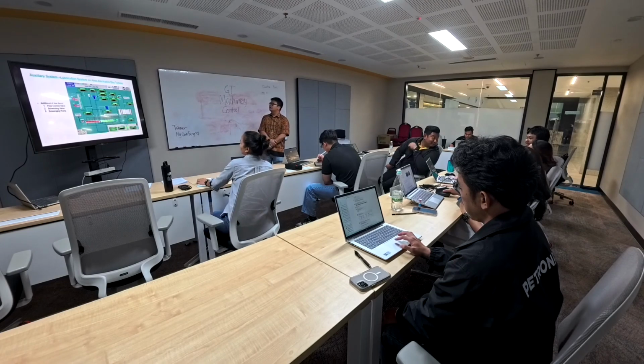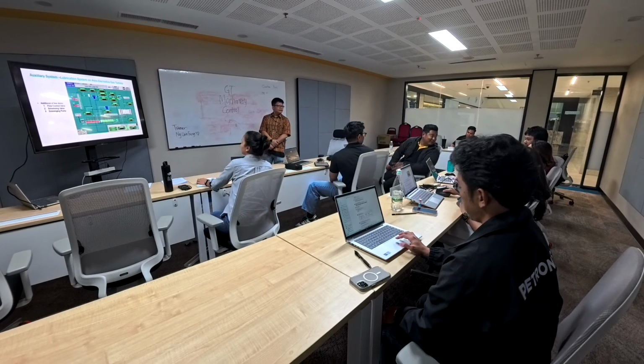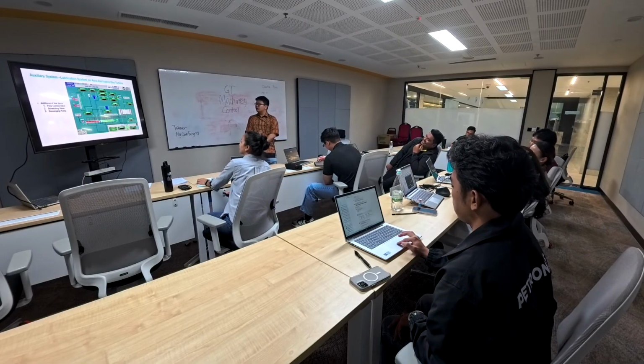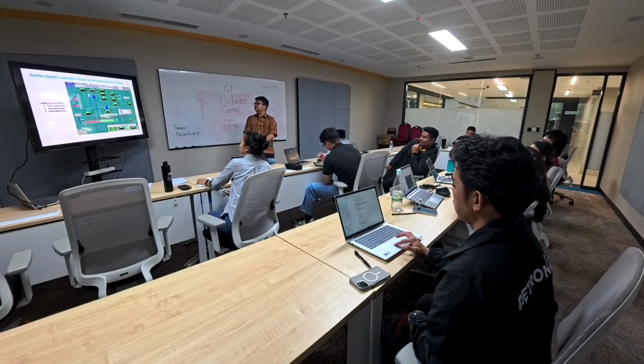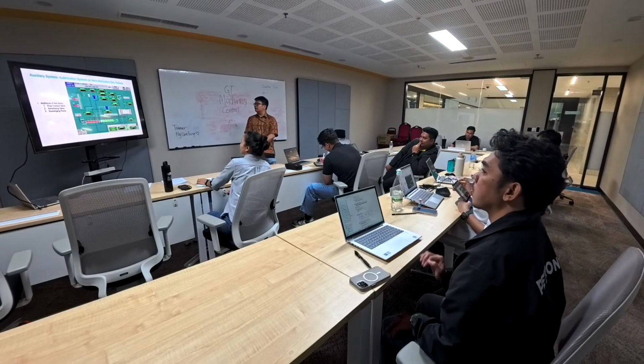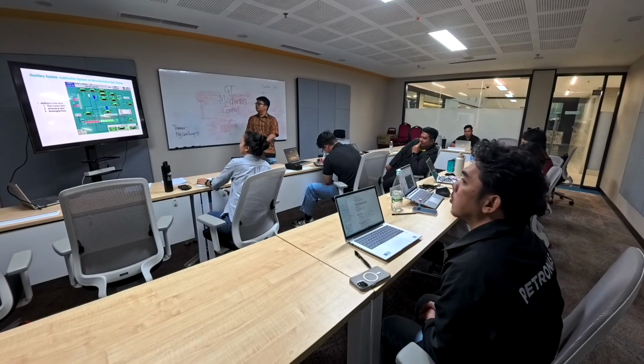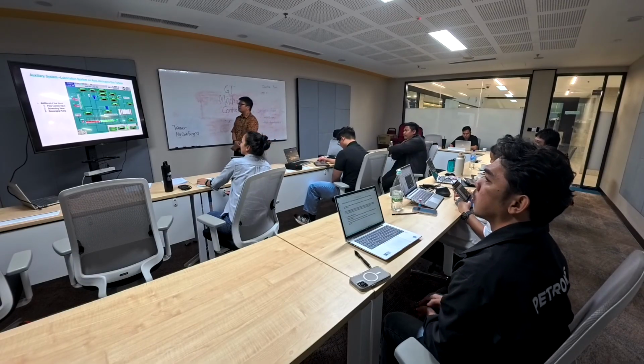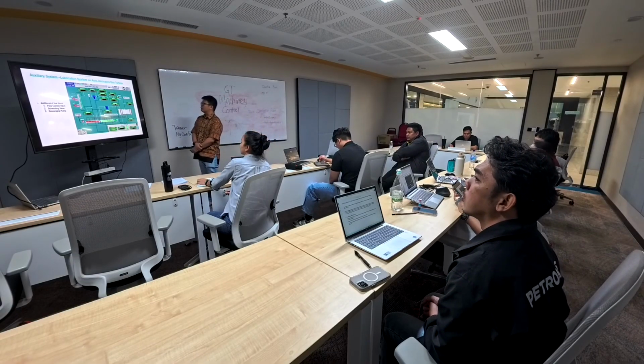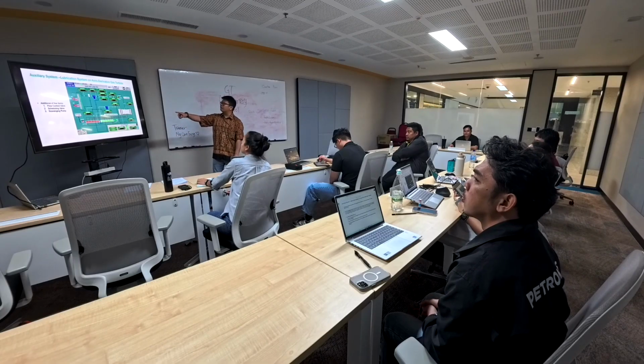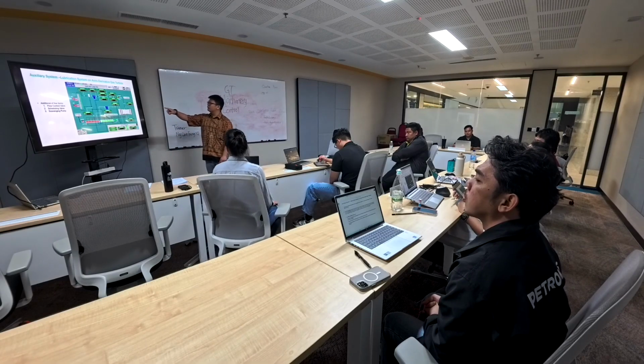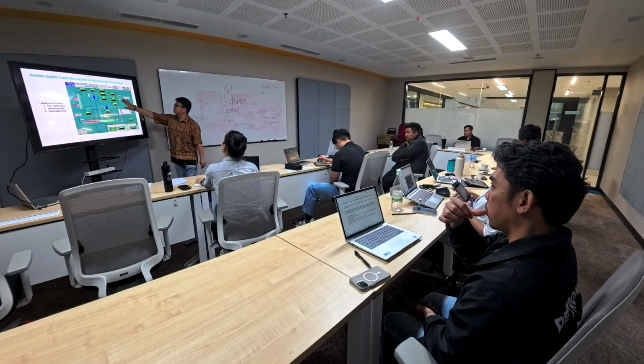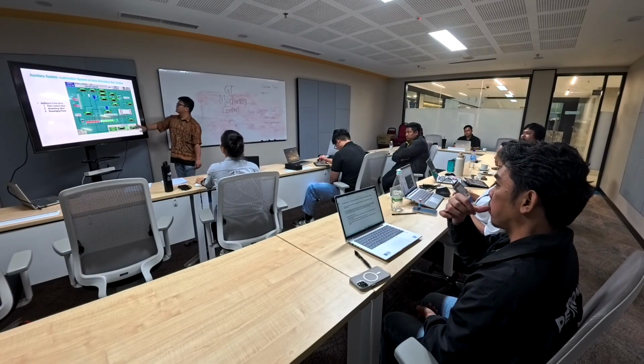Johnson. Okay. This is a typical HMI snapshot for the aeroderivative gas turbine for Siemens RB211. So you have your flow control valve, you have your scheduling valve, and you have your scavenging pumps. I think I've already explained the scavenging pump. So what is the flow control valve and what is the scheduling valve? This is a scheduling valve.